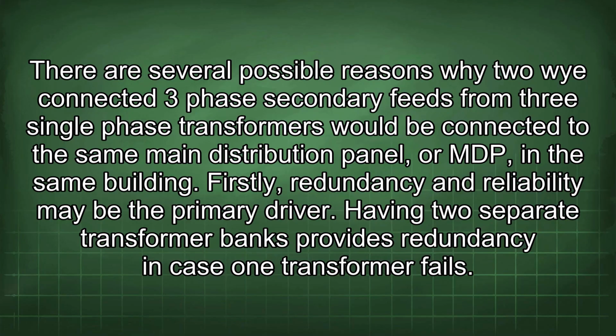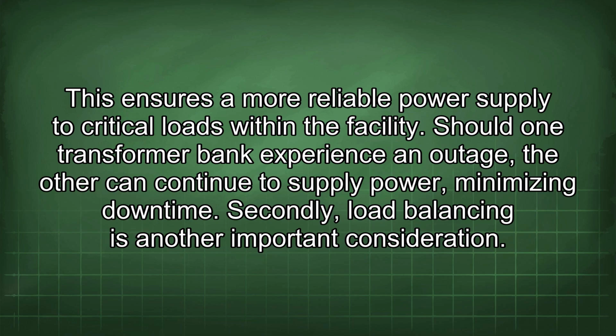There are several possible reasons why two Y-connected three-phase secondary feeds from three single-phase transformers would be connected to the same main distribution panel, or MDP, in the same building. Firstly, redundancy and reliability may be the primary driver. Having two separate transformer banks provides redundancy in case one transformer fails. This ensures a more reliable power supply to critical loads within the facility. Should one transformer bank experience an outage, the other can continue to supply power, minimizing downtime.